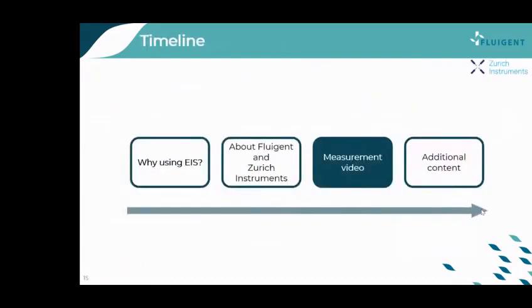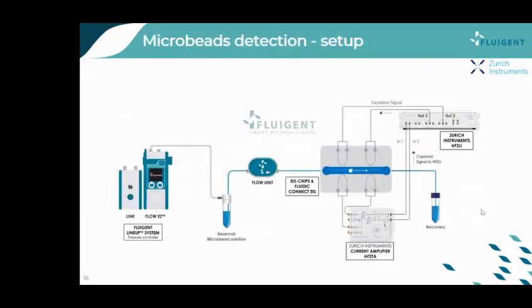Now we have covered the EIS measurement principles and presented our companies and instruments. Let's have a look at the real measurement setup. Here you can find the scheme of the setup to perform measurements on micrometer beads. The lineup system consists of one Flow EZ and a Link. The Flow EZ is connected to the reservoir containing the 20-micrometer microbead solution, which is subsequently connected to the EIS microfluidic device. The tubing passes through a flow unit to monitor and control the flow rate. Once injected inside the chip, the microbeads pass the electrode pairs, and impedance measurements are performed using the HF2LI lock-in amplifier coupled with the HF2TA trans-impedance amplifier.